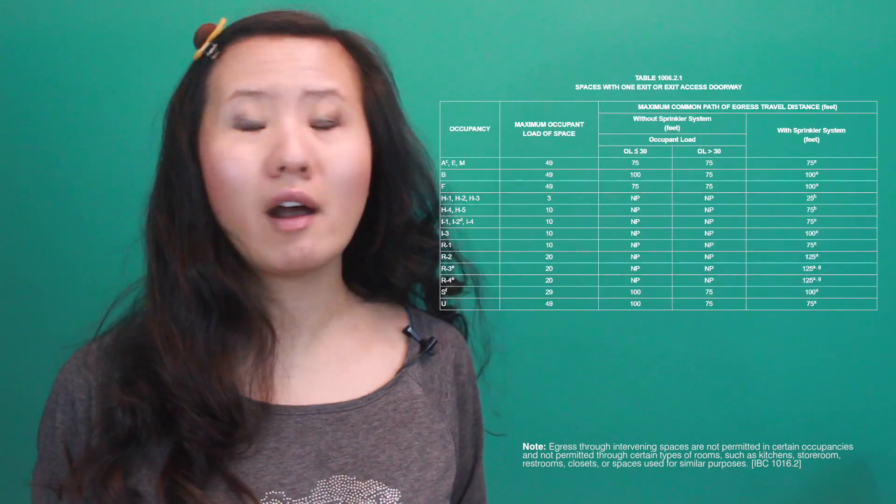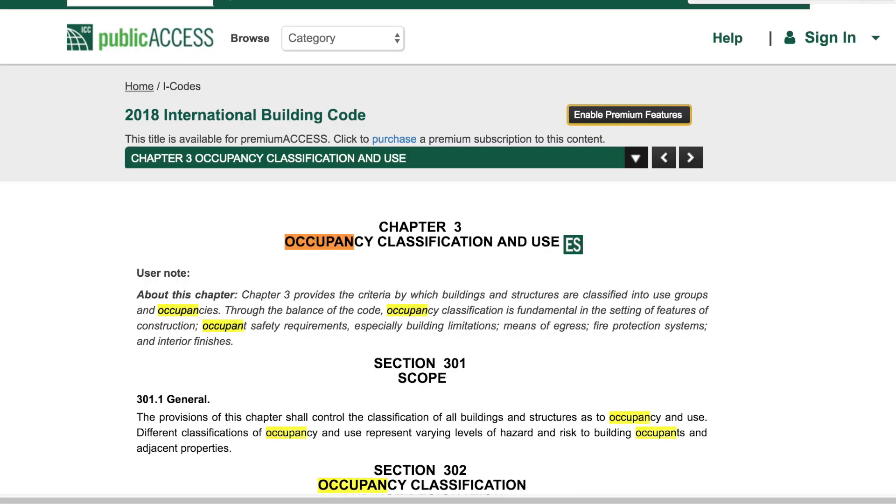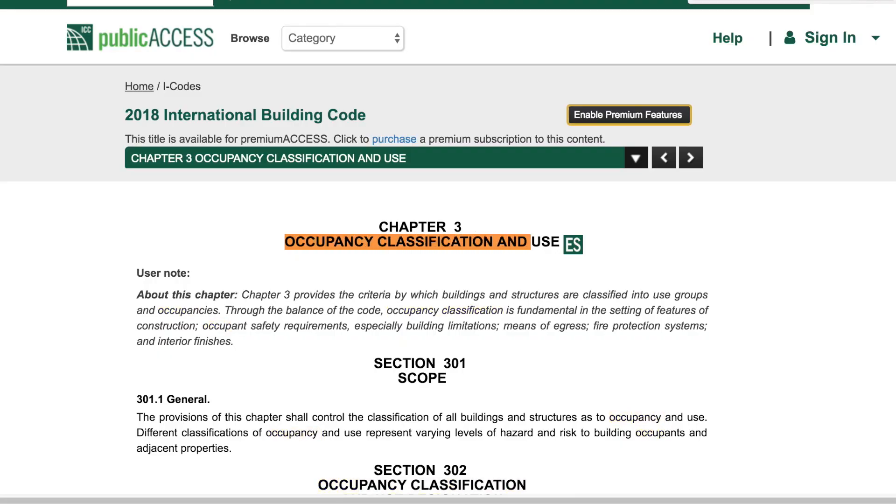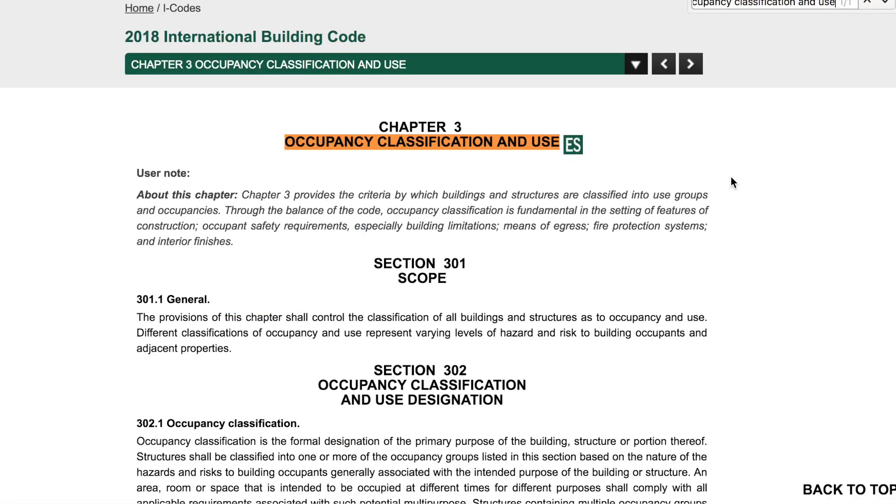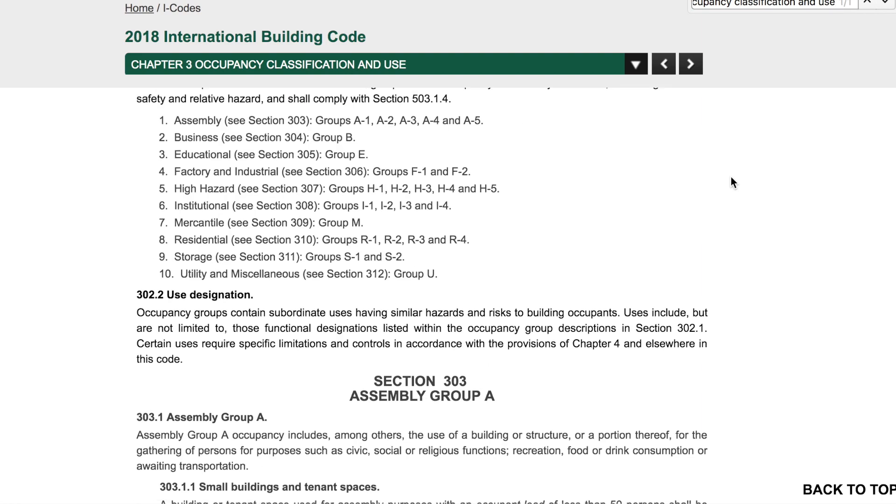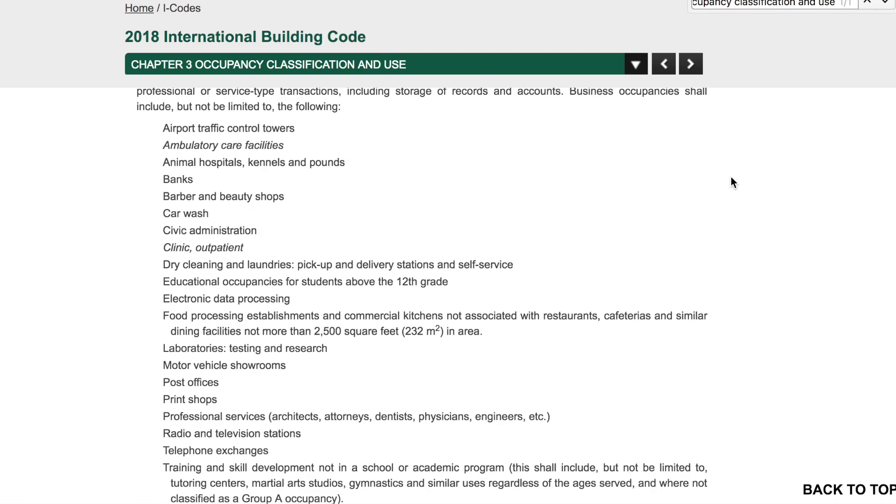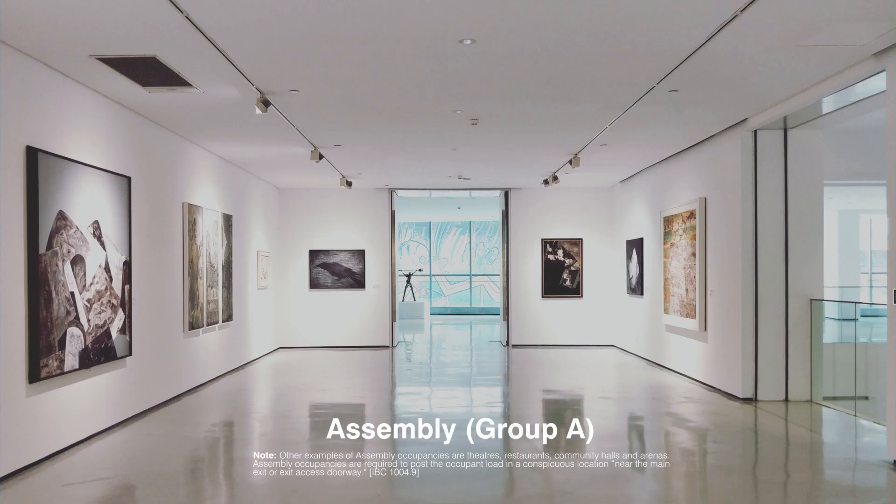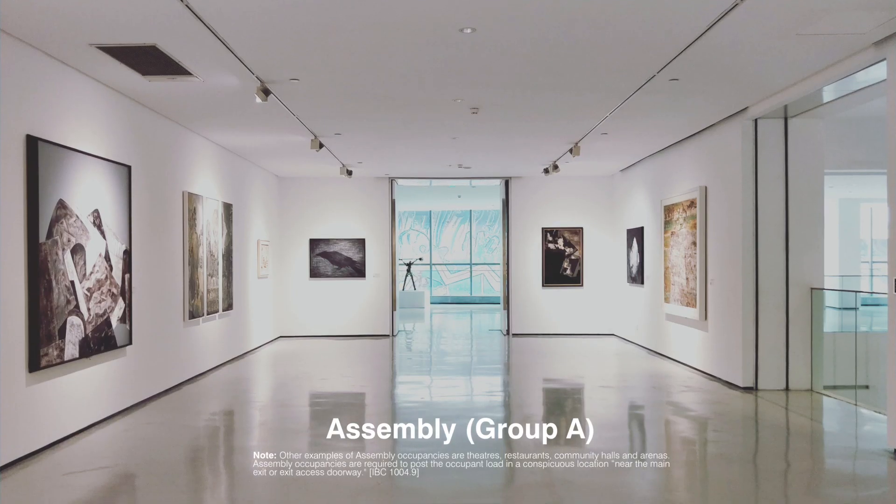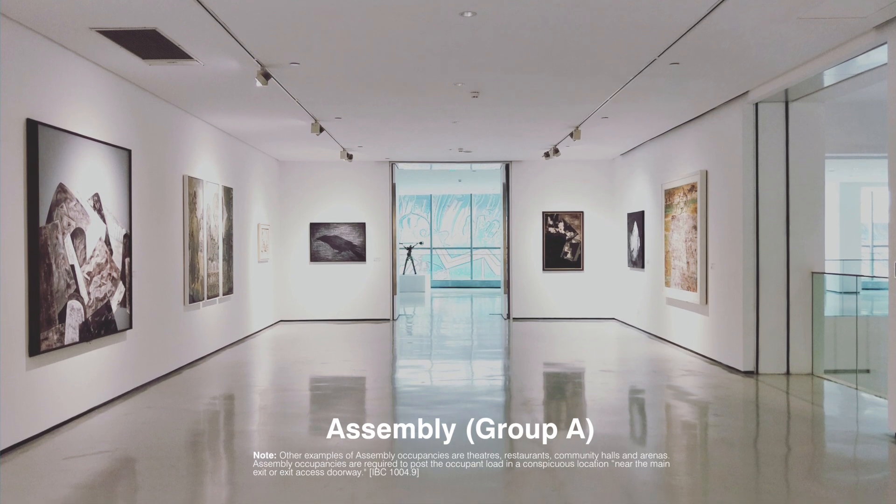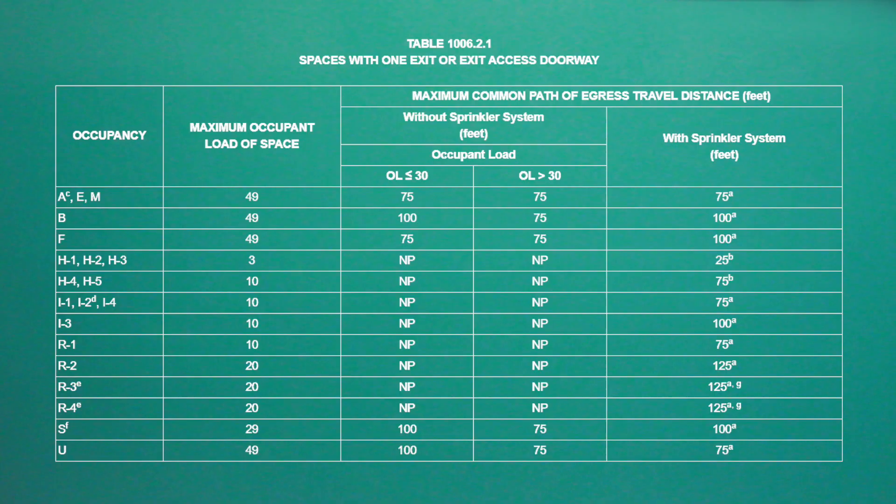So pretty obvious, every space needs at least one means of egress. But two or more means of egress are required if the space exceeds a certain occupant load under certain occupancy classifications. Occupancy classifications are formal designations for the primary purpose of a building or portion of a building.